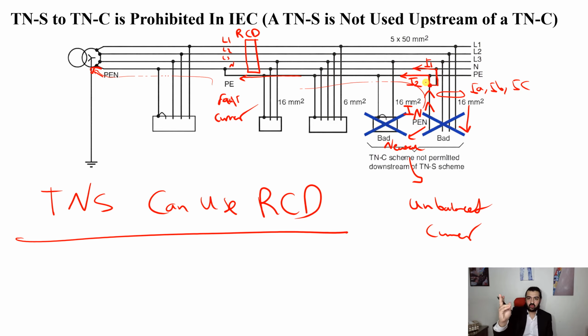So part of it will get back through its normal path, which is the neutral. Another part will go through the protective earth, dependent on the impedance of these two. So one will go like this, all the way like this, and the other one will go all the way like this, and then combine here back to the supply. Everything seems normal. However, PE or protective earth should not have any current except under fault condition, not normal condition.